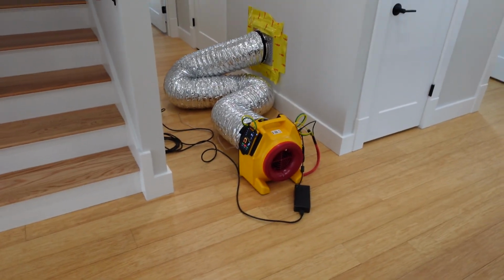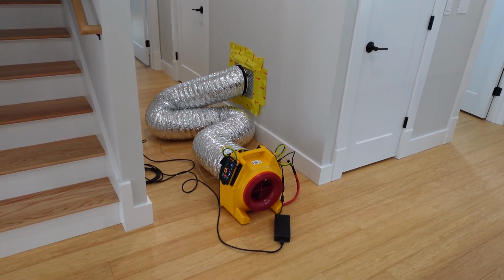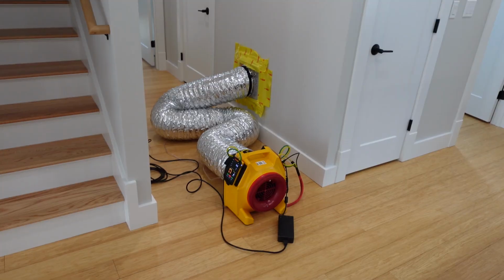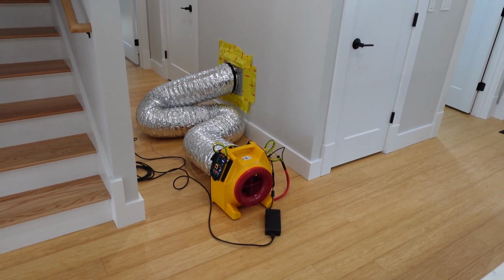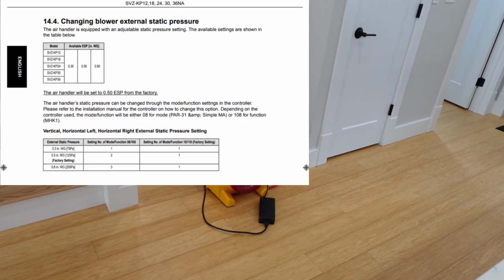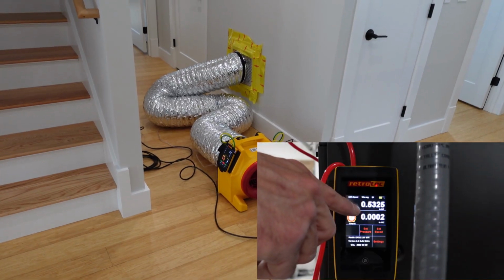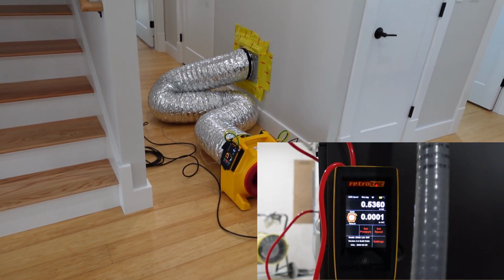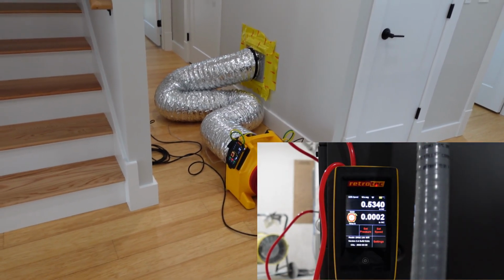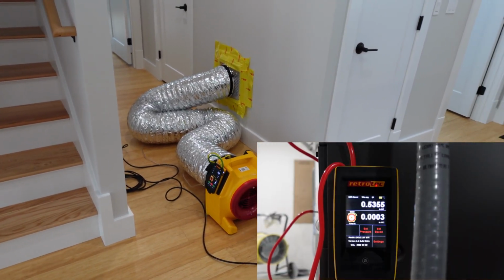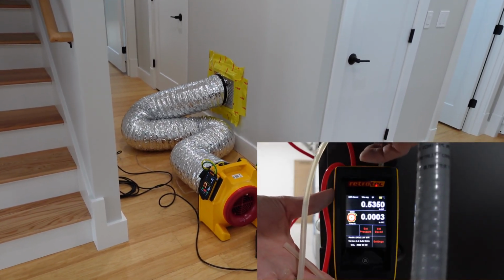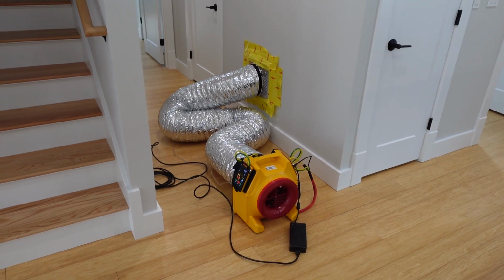The other one is I want to ensure that the system is running correctly. So it's a 2-ton system, should be moving 800 CFM at the high setting, and I believe it's around 400 CFM at the low setting. The static pressure testing showed that it was 0.5 inches of water column, so it should be in the right amount of static pressure. So the total system airflow should be accurate.